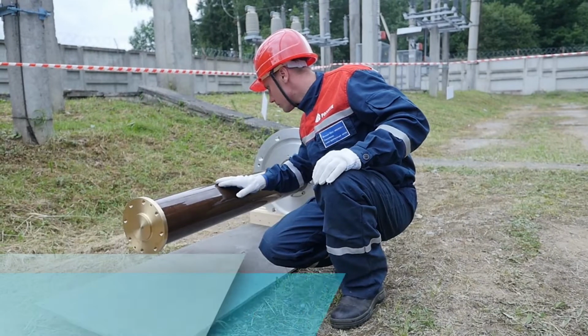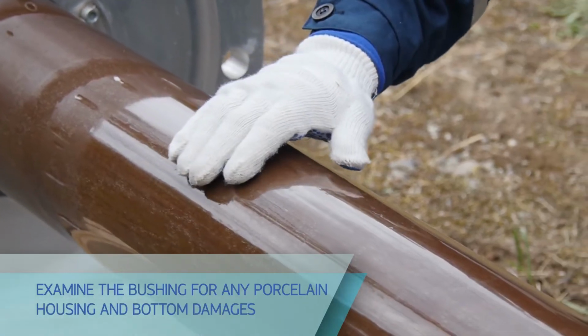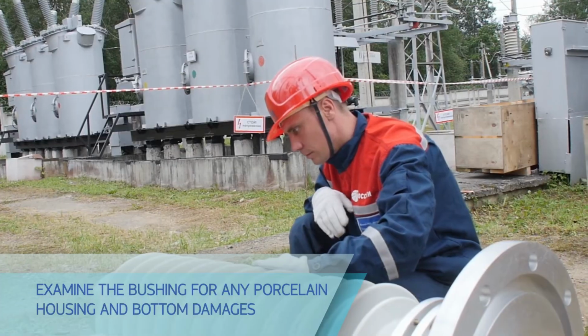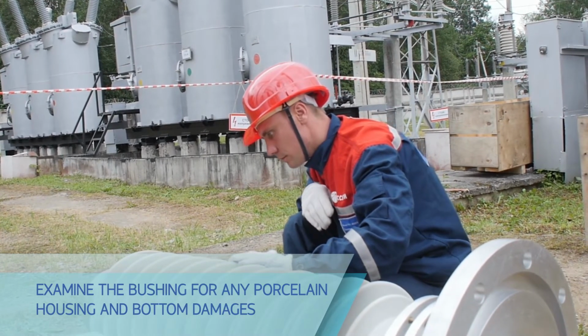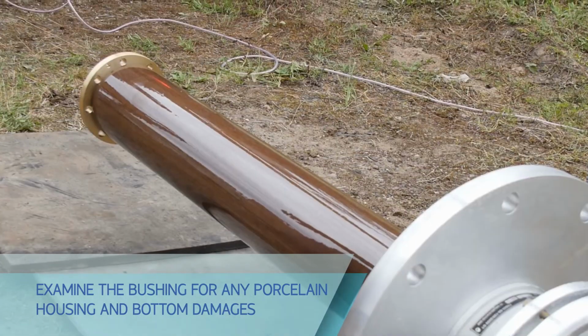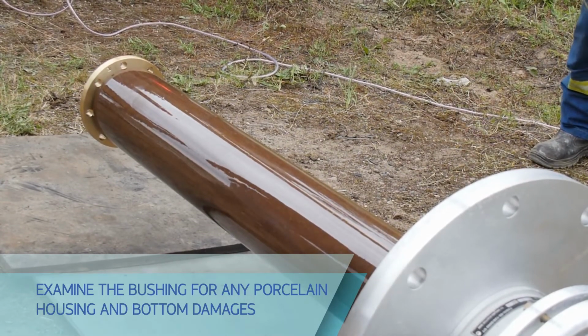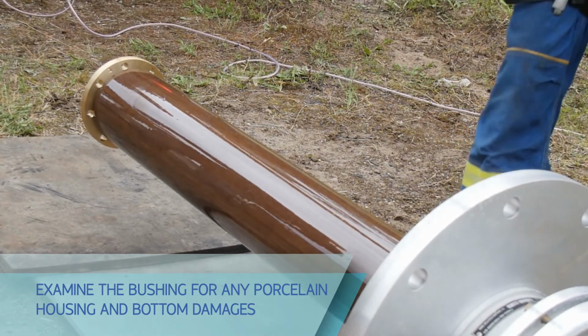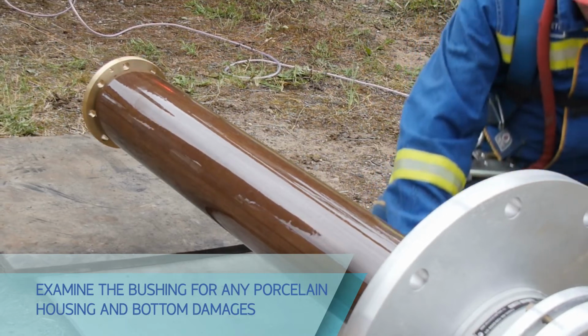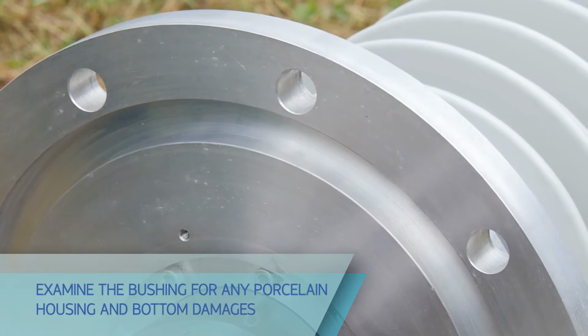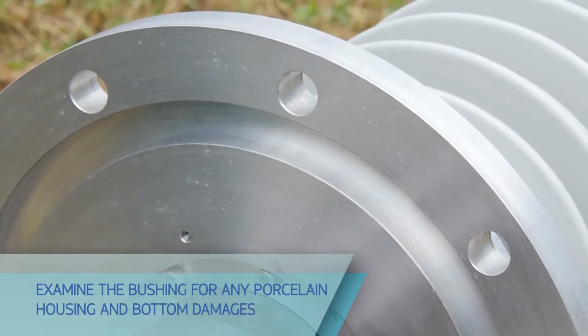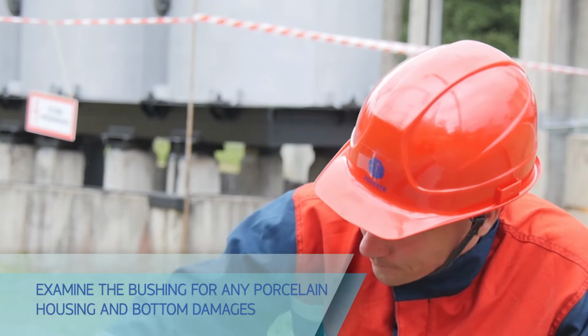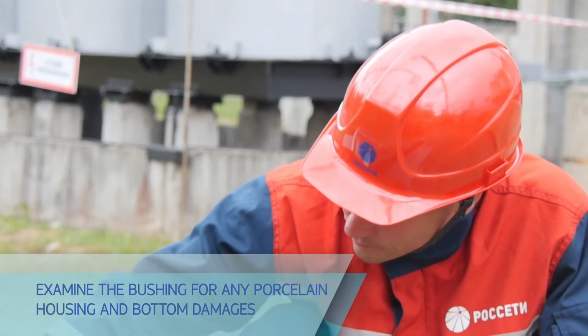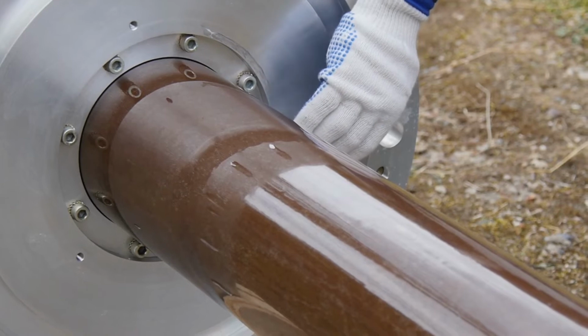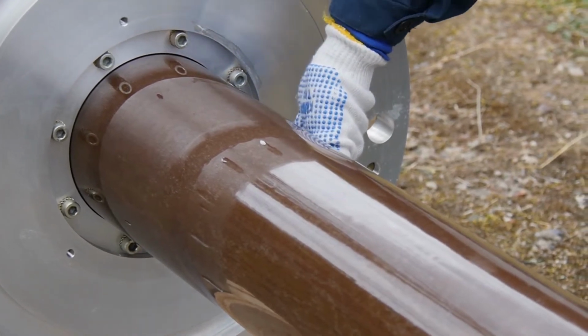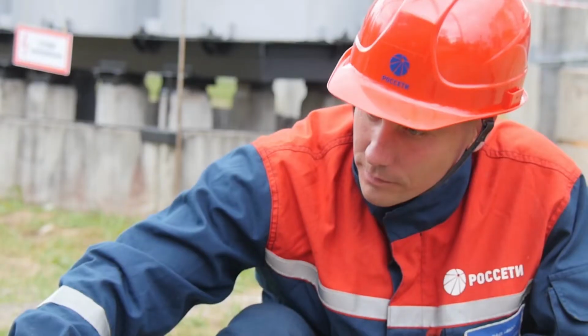None should be found, since any porcelain crack or cleavage might extend later and completely destroy the external insulation, leading to the bushing failure. Bushing components shall be free of oil leaks and damages. The bottom may contain a small quantity of oil left after factory testing. It does not indicate an oil leakage. If necessary, measure dimensions of the bushing units and components, although it is optional. While being manufactured, the bushing is subject to multi-stage inspection, and the manufacturer guarantees its conformity with relevant regulatory documents.